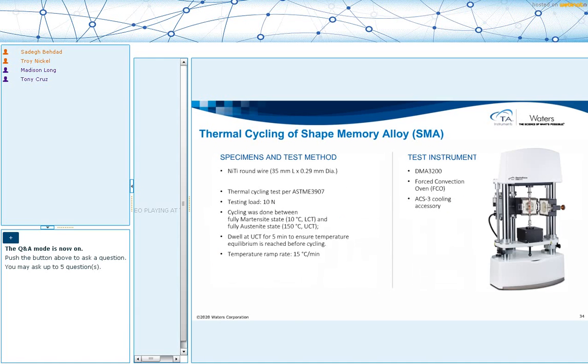So we did this test using a DMA 3200. This is a high force DMA instrument. In this specific example, we are not using it for a DMA test. We're using it because of its oven and its ability to do higher temperature ramp rates. We were testing a rather thin wire, 0.3 millimeters in diameter and 20 millimeters of gauge length, overall length 35 millimeters. And we applied 10 newtons of load. We're testing this between 10 degrees C and 150 degrees C at a rate of 15 degrees C per minute. So a very fast experiment here.